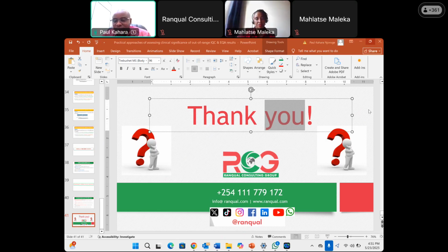The IQC fails. So go ahead as a team, halt the patient testing, don't be in a hurry. Try to ask yourself whether you are going to do it by 5 whys or by the fishbone diagram. Try to ask yourself, is it about the equipment? Is it about the personnel who ran it? Is it about the storage? Is it about the environmental conditions? So I may not have a straight answer on why IQC fails, because they're going to fail for different reasons at different times.